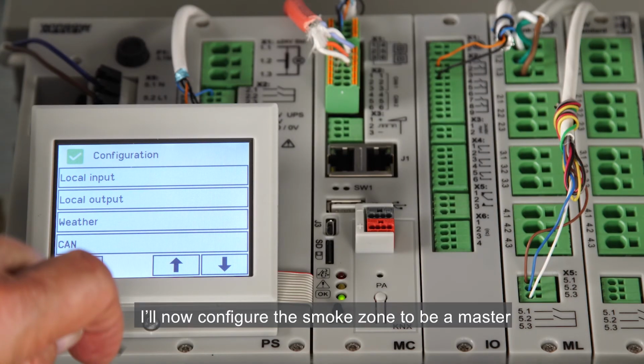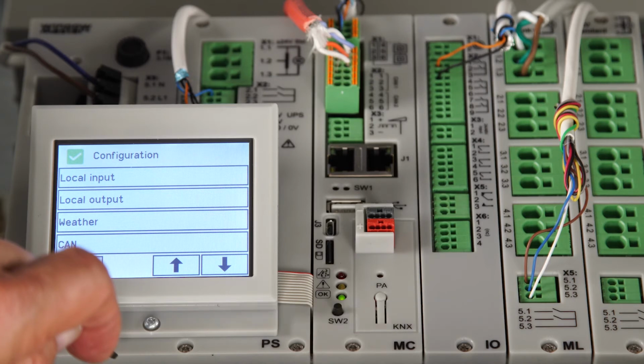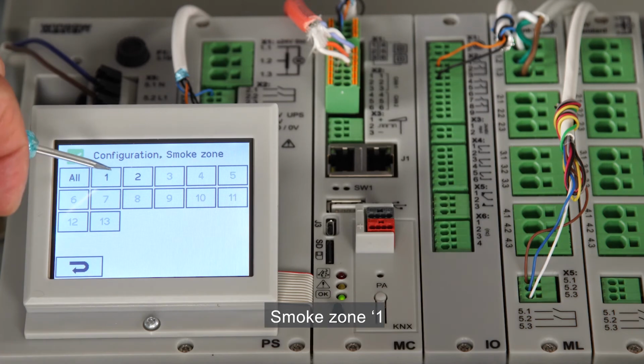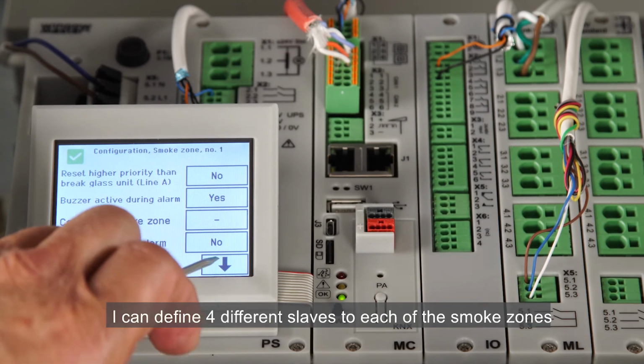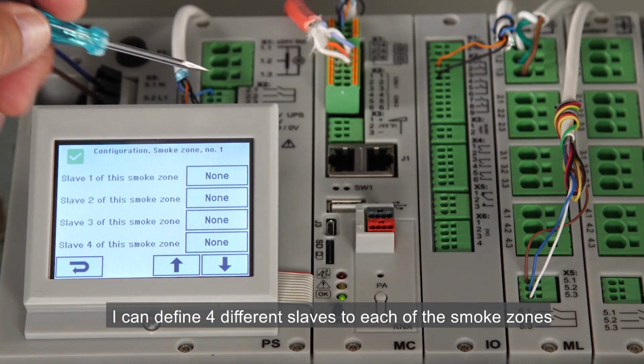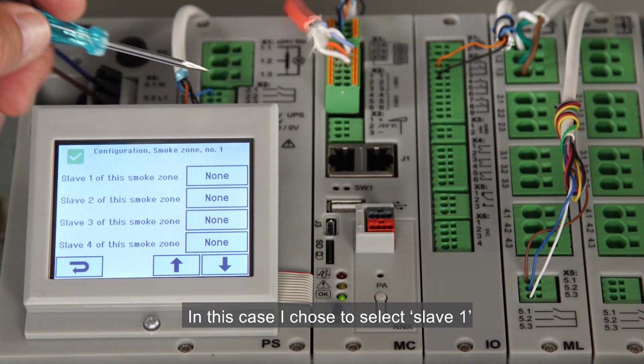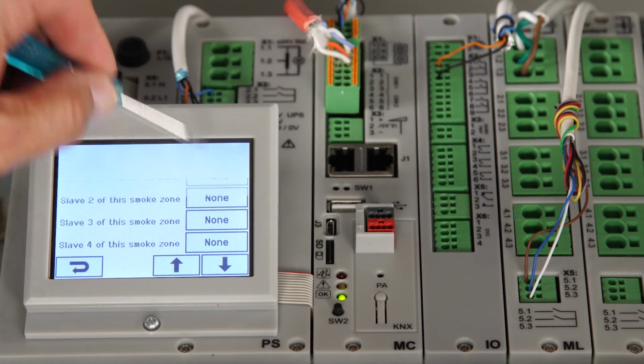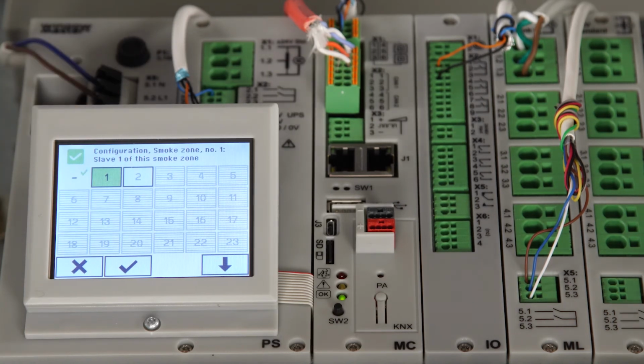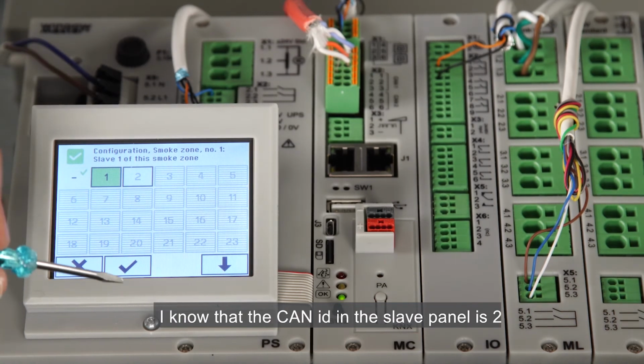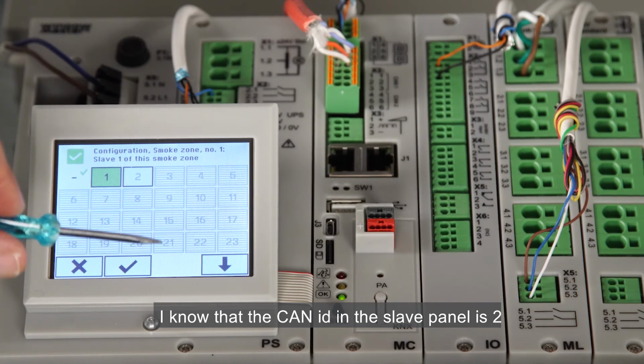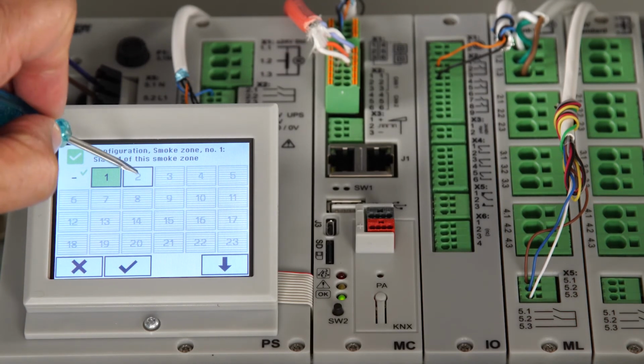I'll now configure the smoke zone to be a master. From the configuration menu, I select Smoke Zone 1. I can define 4 different slaves to each of the smoke zones. In this case, I chose to select Slave 1. I know that the CAN ID in the slave panel is 2, so I select 2.